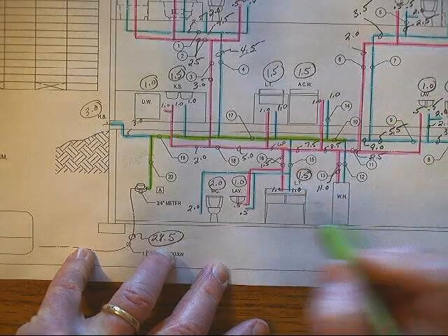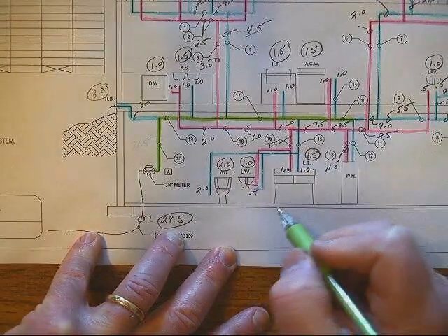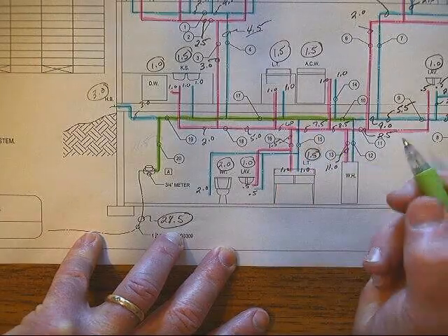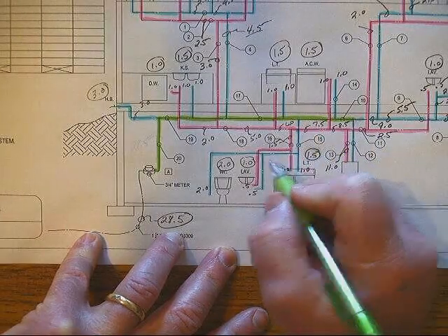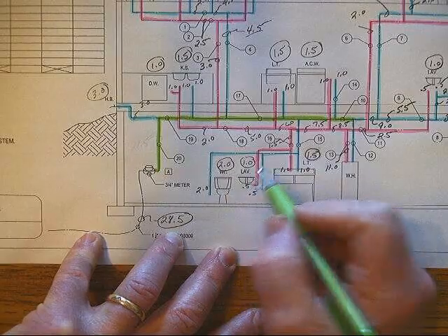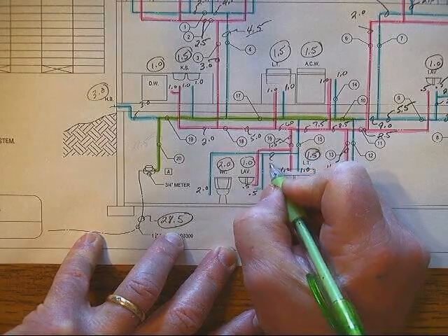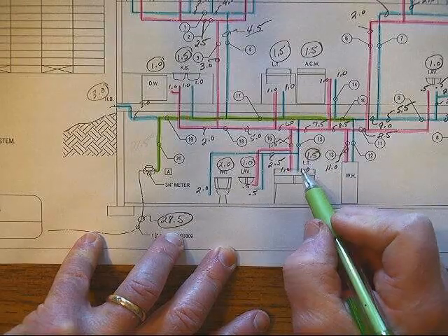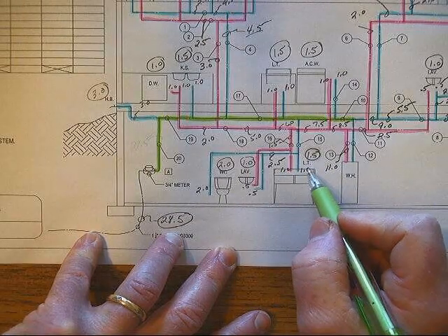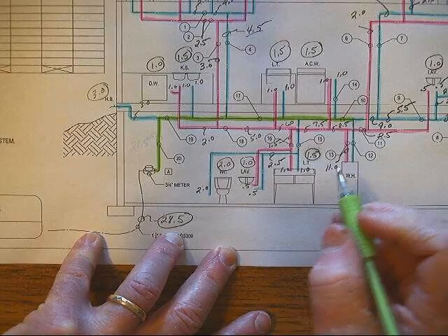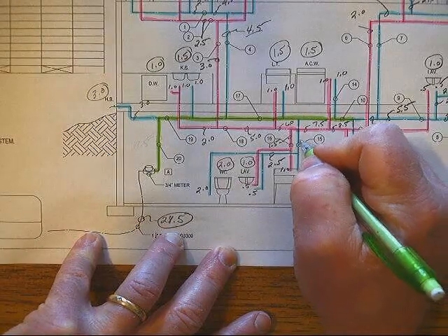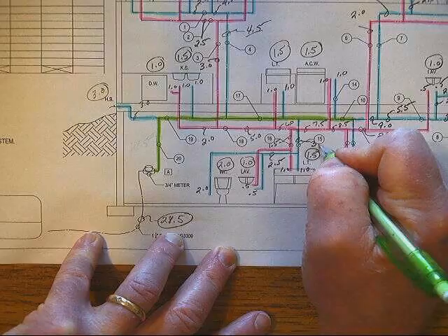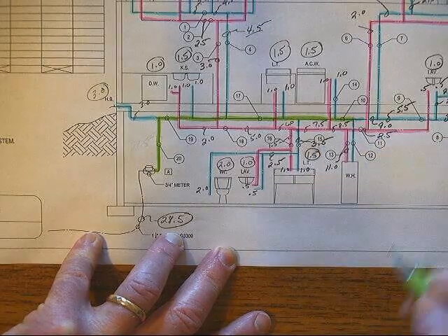The only thing left would be the piping in the basement. The piping in the basement for the lav and the water closet right here would have a total of 2.5 on it. That 2.5 would join together with the laundry tray, and we would now have 3.5 at that point.